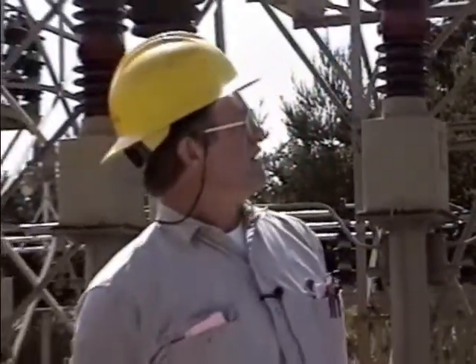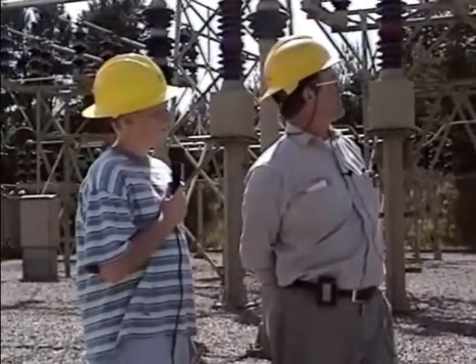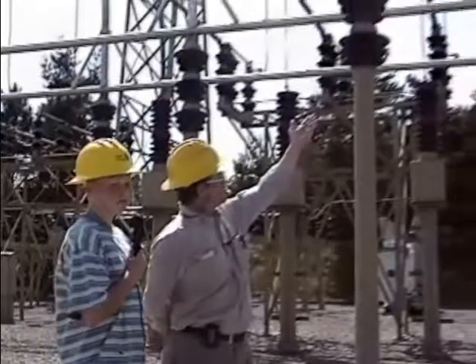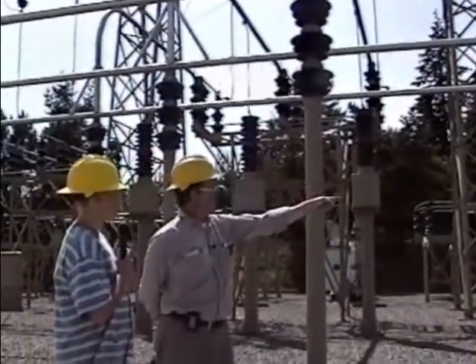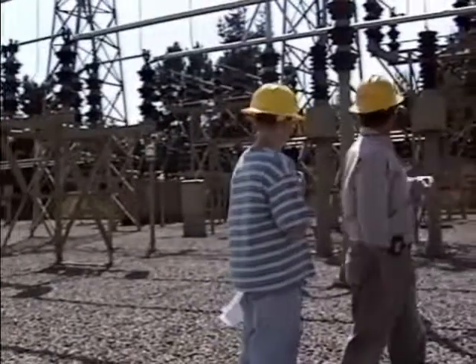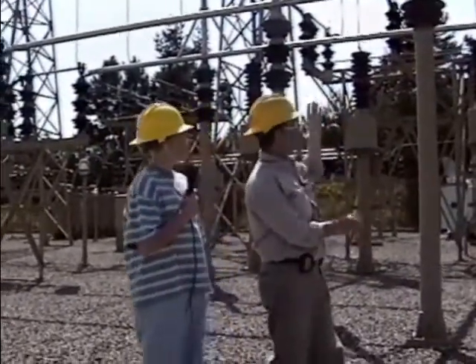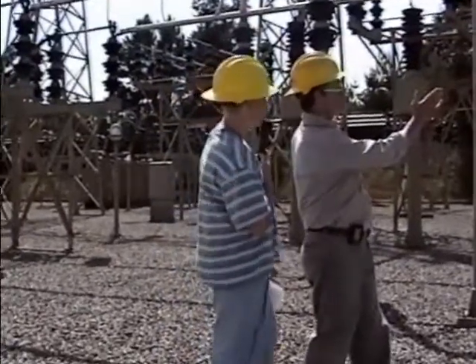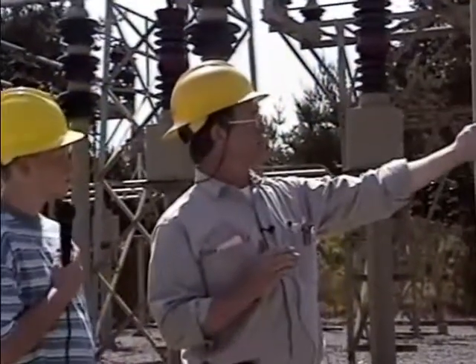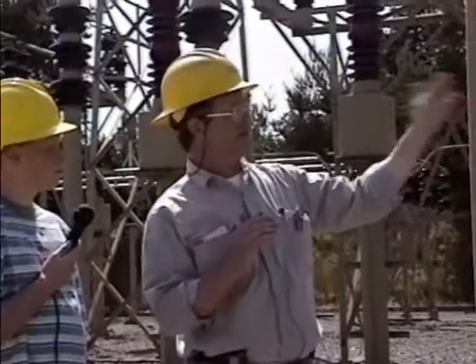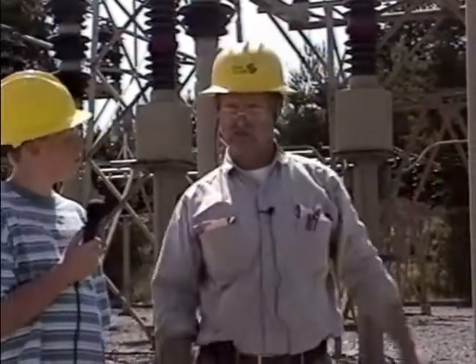What happens if one of these breakers or something breaks down? Do the other ones act as a backup to it? Yes, that's exactly what happens. If something happens in this station, let's say something up there would break and you get a short to ground, that breaker would open, and the breakers connected to it would open to isolate this piece of equipment. Now if something else would fail, say that breaker for some reason wouldn't open, it would just go one step beyond, and the breaker beyond it would open. It just isolates the trouble.